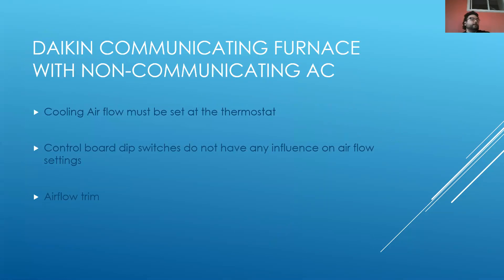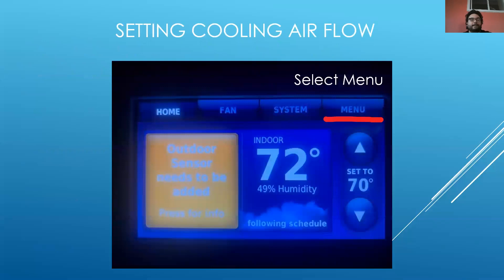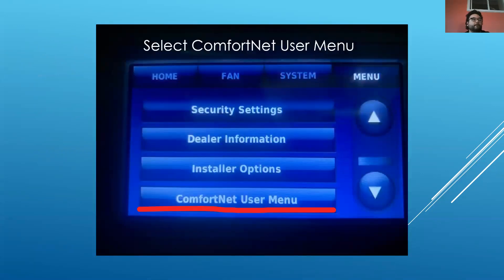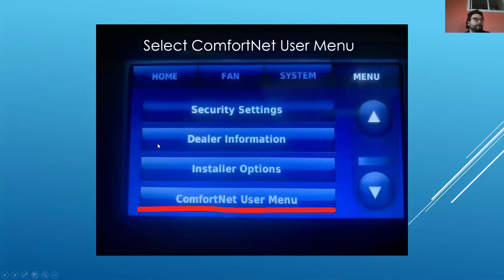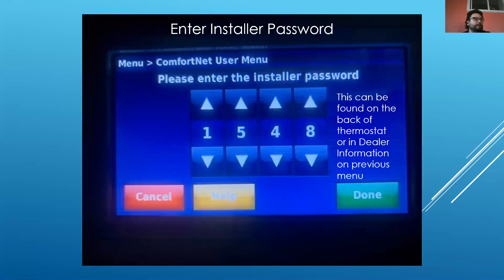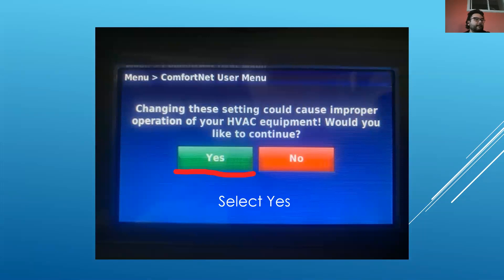With a non-communicating air conditioner, we have to set the cooling airflow at the thermostat. It doesn't matter what you do down at the board or anything like that — you have to set the airflow and trim at the stat. So we'll go to our CTK-04 screen, select our menu button, and go down to the Comfort Net user menu. We'll type in our dealer code. If you don't have the thermostat dealer code, go to dealer information and click on that — you'll get the four-digit code without having to pull the stat off the wall. Put in the number and hit yes to change settings.